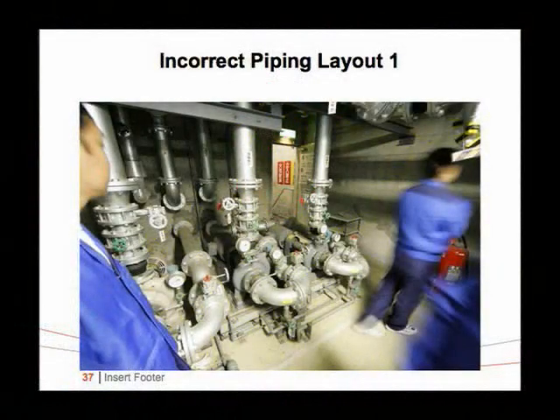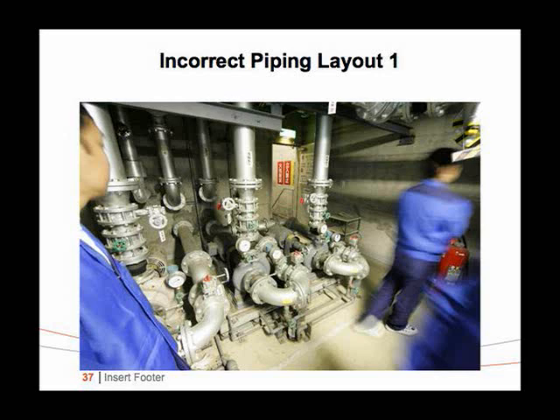Going back to Japan, this is all stainless steel fittings, so it's not really very cheap. You look at the number of elbows. When you enter a pipe like a pump like this, you're going to have a tremendous swirl on the inlet, and I've made this mistake myself, so I can tell you, you will lose a lot of pressure development on the pumps. You should actually turn the pumps and have them facing the entry at the wall, and then you have a straight shot and eliminate that. But my brother-in-law sells stainless steel fittings, so.